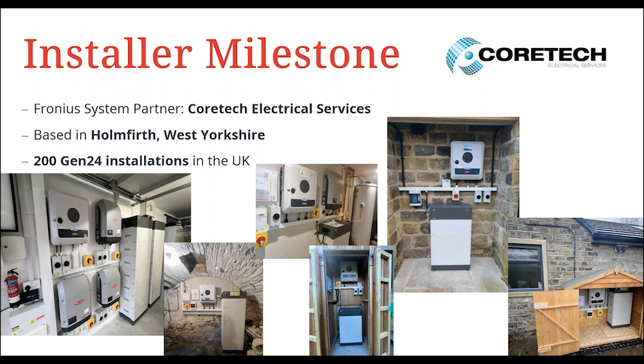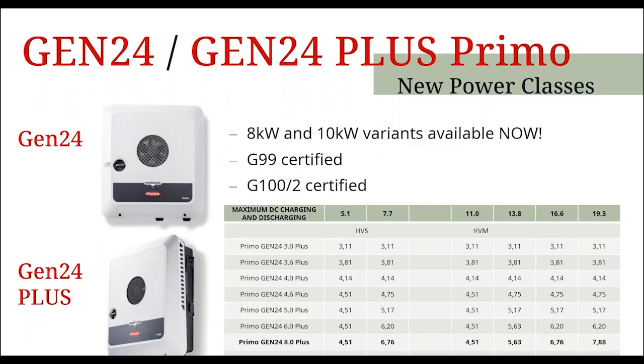Great, thank you. Ian says that your slide with the battery compatibility with different inverters didn't show the data for the 10 kilowatt inverter. I don't know if that was just on the screen, but we will share the details afterwards. Sorry if it's cropped off the bottom of the screen. Apologies for that. It's actually almost identical to the 8 kilowatt unit. So you're looking at 6.76 kilowatts of power from a 7.6 kilowatt hour HVS battery, and you're looking at 7.88 kilowatts of power from a 19 kilowatt hour battery. So just under 8 kilowatts of power with that. Lovely, thank you. We can send those details to you afterwards as well, Ian.